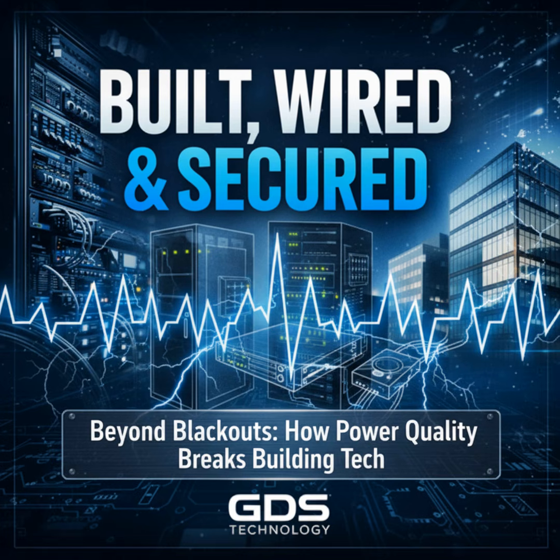Localized solutions, like dedicated tenant circuits, point-of-load UPS or PDUs, and surge protection, are lower cost and quicker to deploy, but don't solve building-wide harmonics. Prioritize by asking, how often does it occur? What is the tenant impact when it happens? And what's the cost of repeated operational response? That triage tells you whether to patch operationally or escalate to capital.